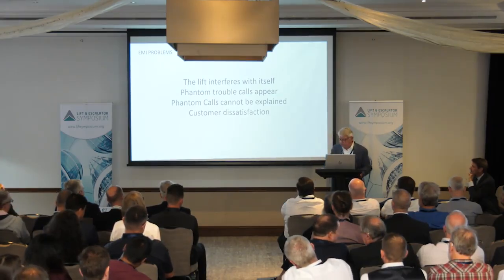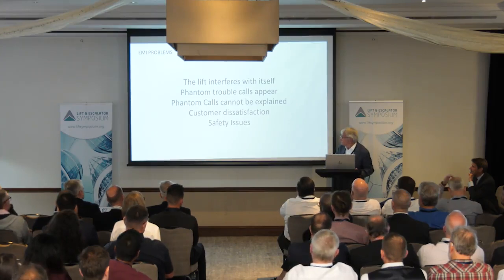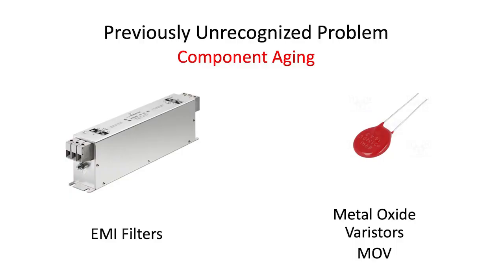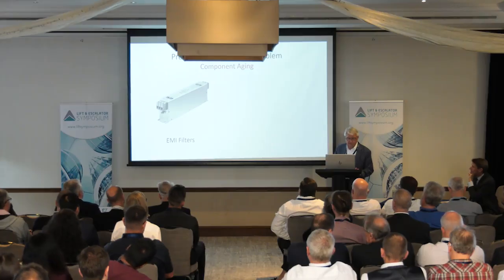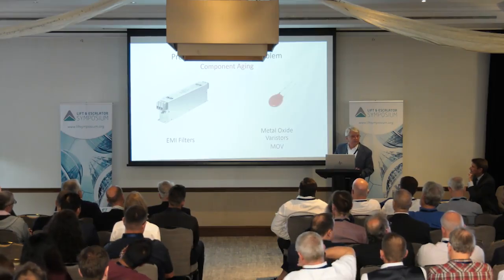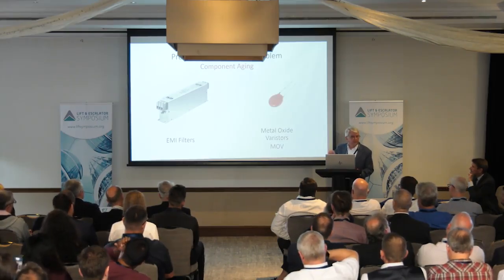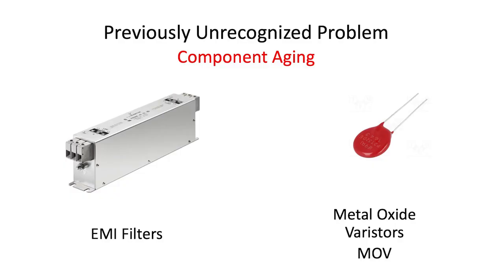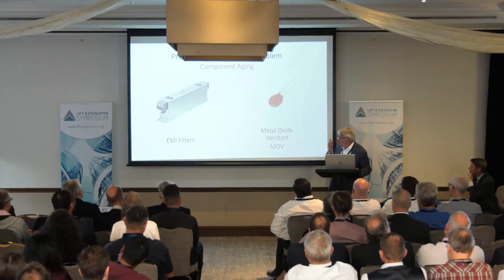One of the things we discovered is that it was a previously unknown problem. There's component aging that occurs in these EMI filters, and they age over time. Also, metal oxide varistors: basically every time there's a transient, it burns a little hole in the thing, and pretty soon it's full of holes and can't absorb any more energy, and they need to be regularly replaced. The same is true with the main EMI filters.